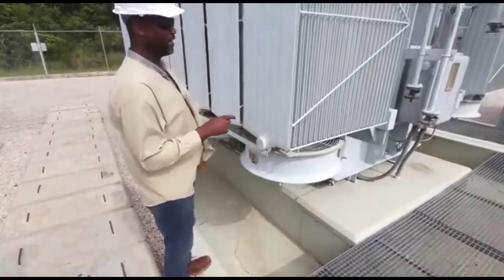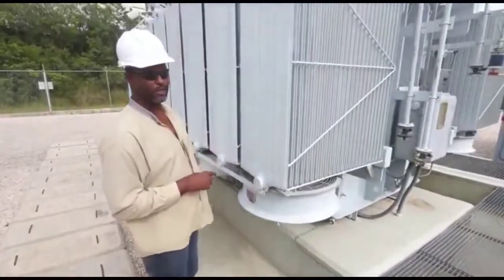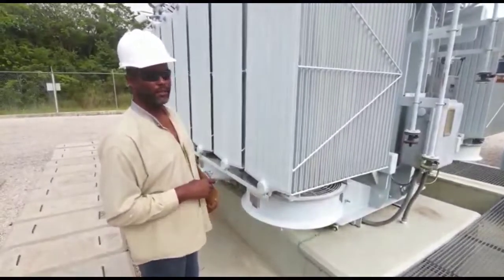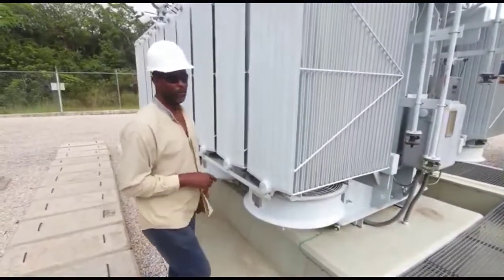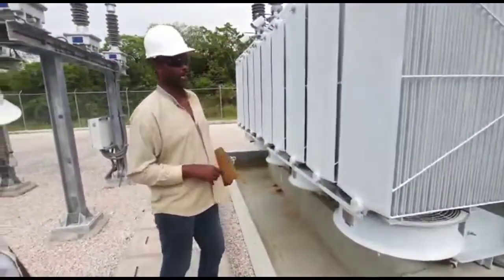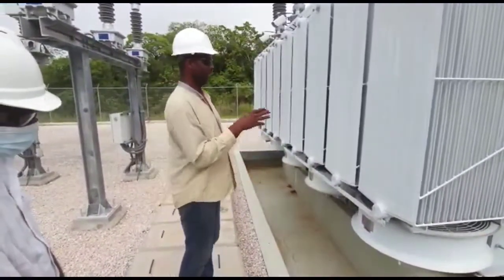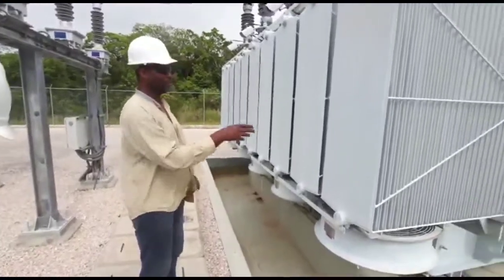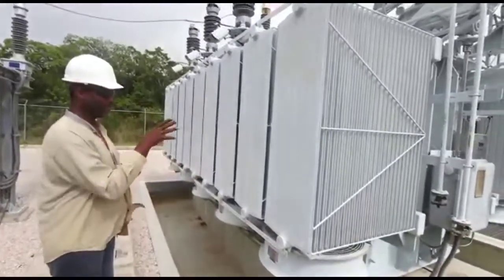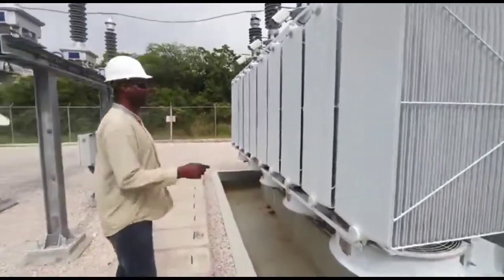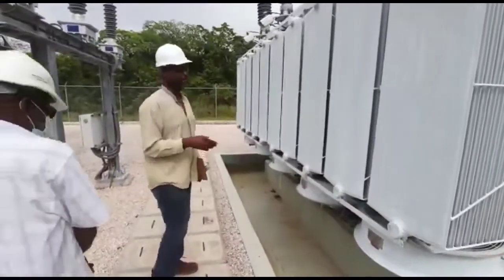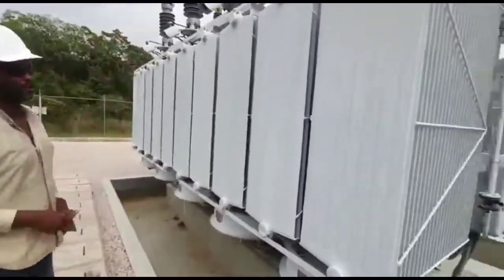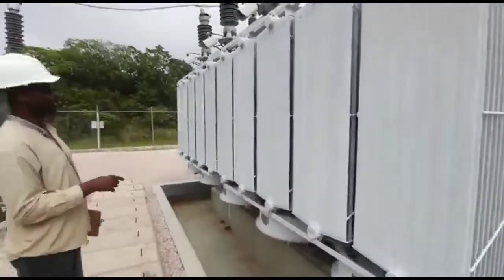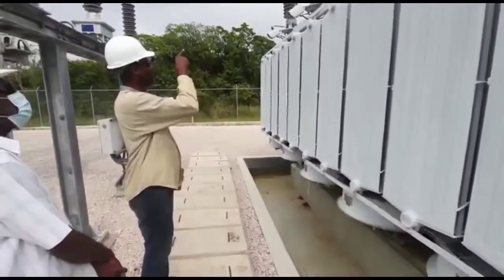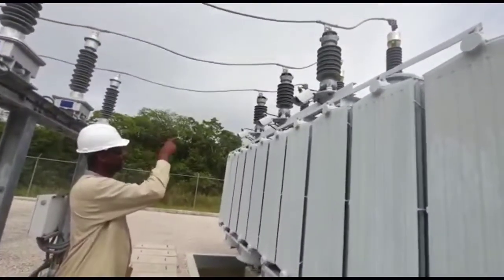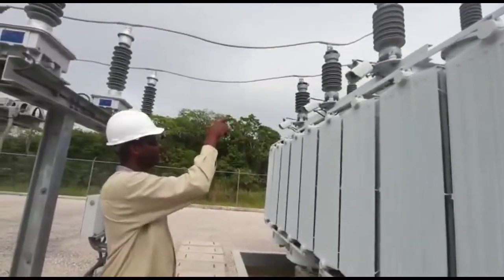And the purpose of the radiator and the cooling fan is for cooling the transformer when it gets above a certain temperature. So once it's working on load, it will get hot and the fans will chip in and cool the radiator, which in turn cools the oil that flows through the radiator and cools the transformer. And this radiator on both sides, this is the high side of the transformer. And on the next side, you have the low side of the transformer. At this side of the transformer, we have 69 kV that you see come here. You have surge arresters and you have CT bushings.